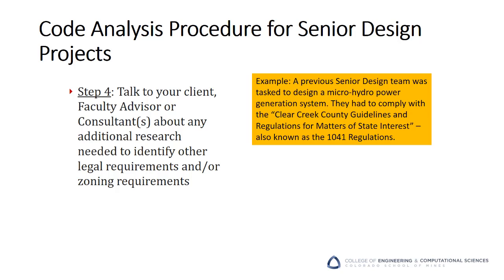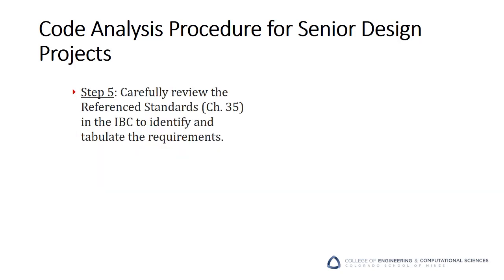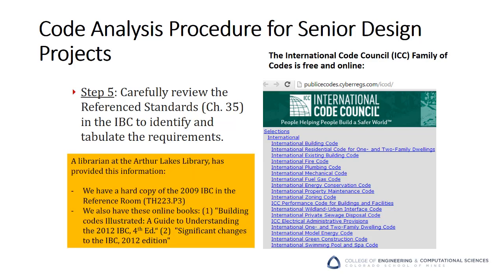An example of these types of other requirements: a previous senior design team was tasked to design a micro-hydro power generation system. They had to comply with the Clear Creek County guidelines and regulations for matters of state interest, also known as the 1041 regulations. After you've completed this process, you may find that state requirements conflict with some local requirements. If that happens, you should constrain yourself with the most stringent of the two requirements. Once the required codes are clearly identified, you'll need to review the reference standards that the code points to. The ICC family of codes is free and available online.